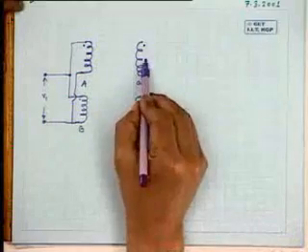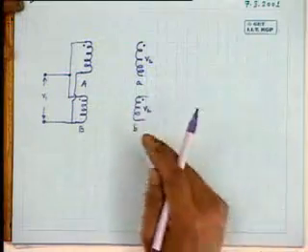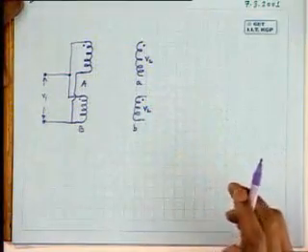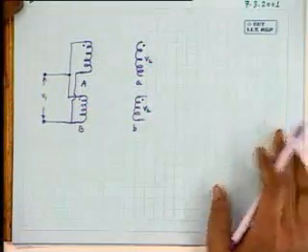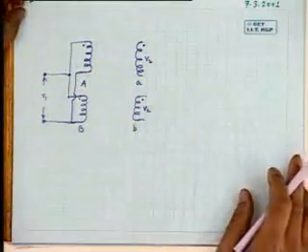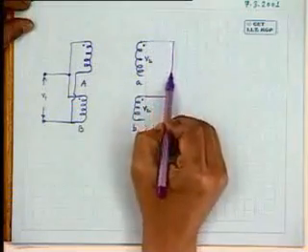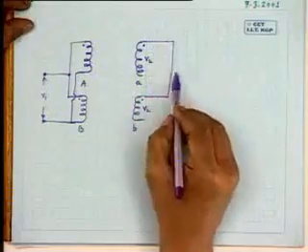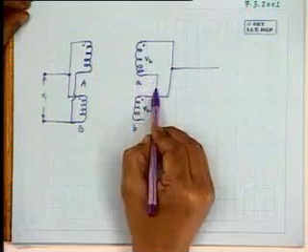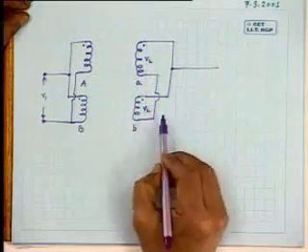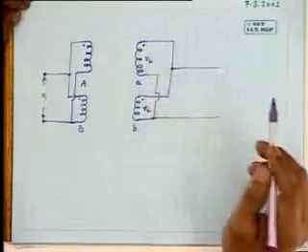Then if you do that, there will be induced voltage across each of the secondaries, because voltage ratings are the same, so V2 volts will be developed. Now these two windings are also connected in parallel. So the second point, the polarity point, is that the correct connection will be like this. These two you join, that is dot to dot, this you take for supplying the load, and these two you join, and this one you take for supplying the load. This is the correct connection.